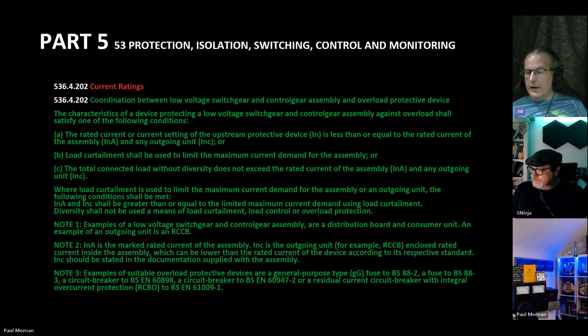And where load curtailment is used, and that's basically where things are going to be switched off if the current goes over a certain level, a good example is electric vehicle charging again. So where that's used to limit the maximum current demand for the assembly or outgoing unit, these following conditions shall be met. InA and Inc shall be greater than or equal to the limited maximum current demand using load curtailment. Diversity shall not be used as a means of load curtailment, load control or overload protection.